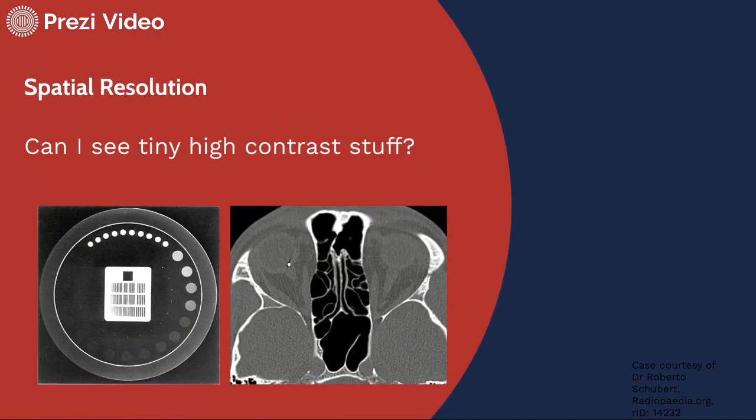Spatial resolution is just asking the question, can I see tiny high contrast stuff? Here's an example from CT where we might measure it using the CT phantom looking at the line pairs at the center. But then here is a CT scan of facial bones, and we're looking at this little tiny metal sliver at the center. Can we see that little tiny high contrast metal sliver? We know it's high contrast because it has a high atomic Z number in comparison to the soft tissue structure that it's embedded in.